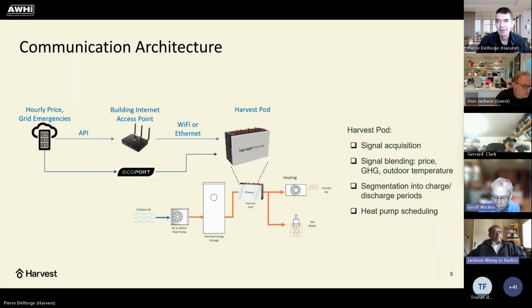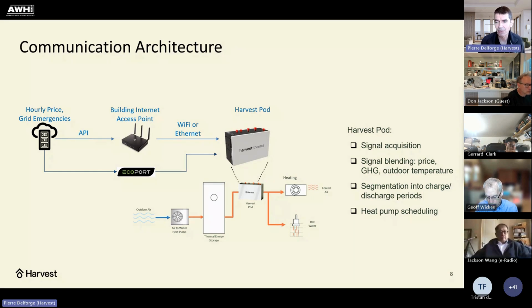Absolutely, yeah, this is great. We have a lot of sensors in the pod that, for control purposes, are how we control the different components. Those sensors give us the minute-by-minute draw profile for both heating and hot water, every minute since the system was installed. So we're able to use this with some relatively simple machine learning to construct the demand forecast for the next 24 hours.